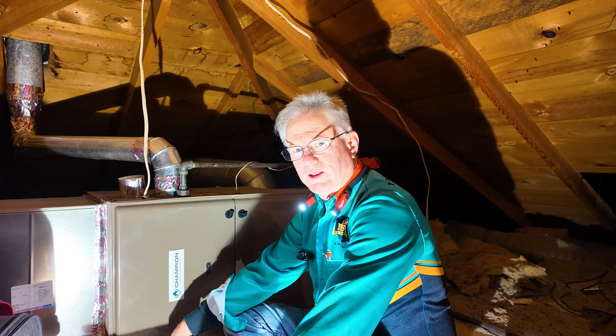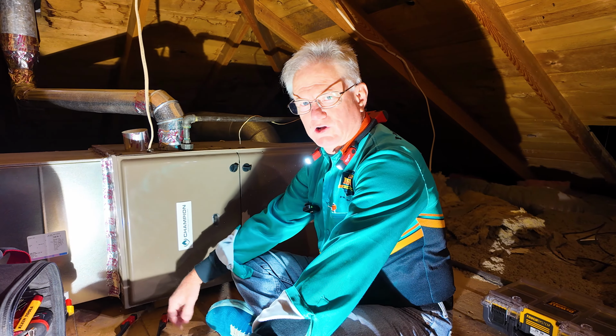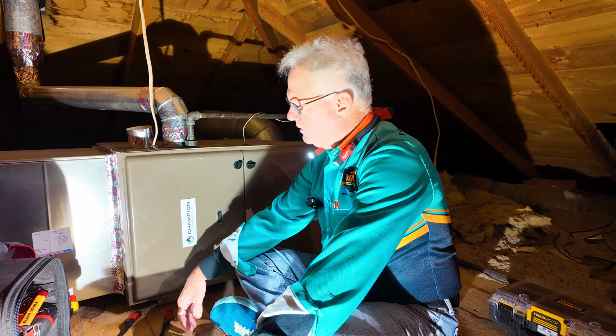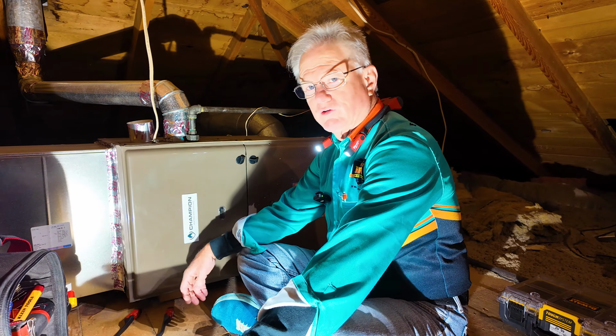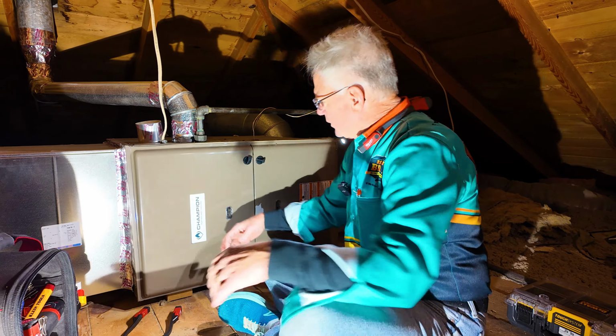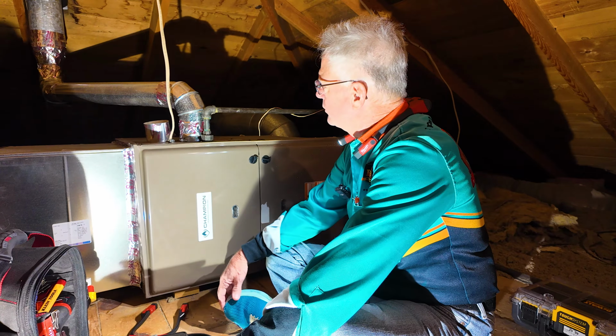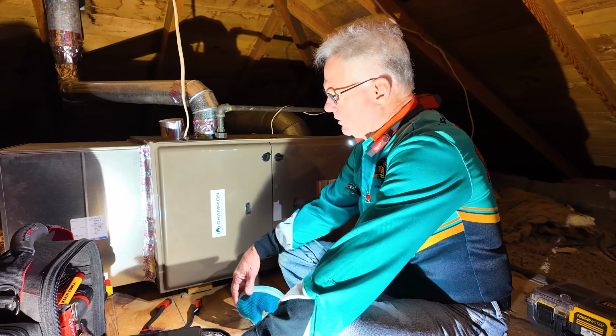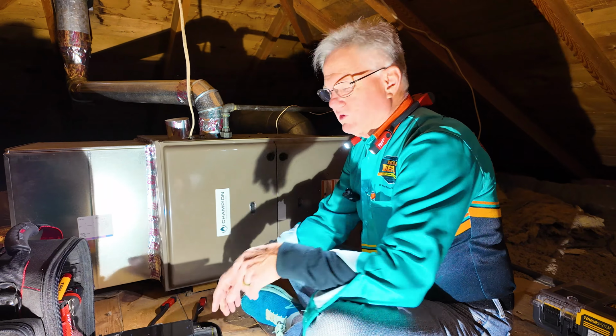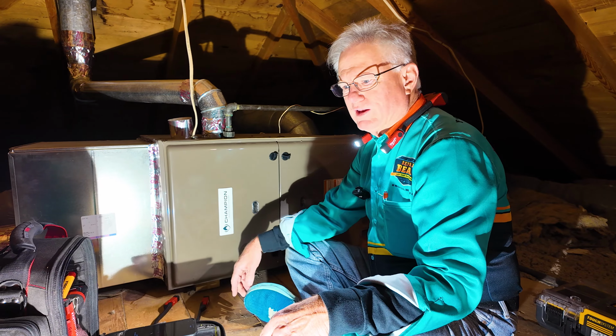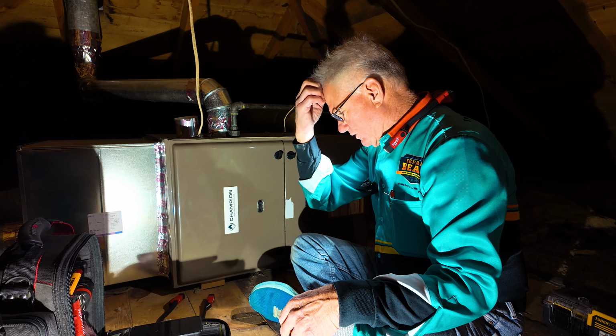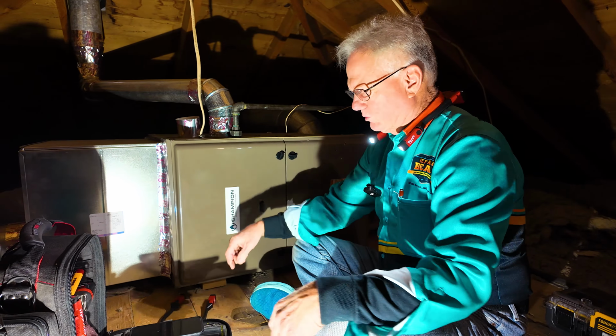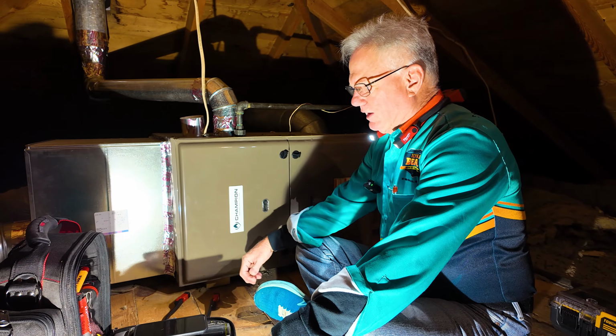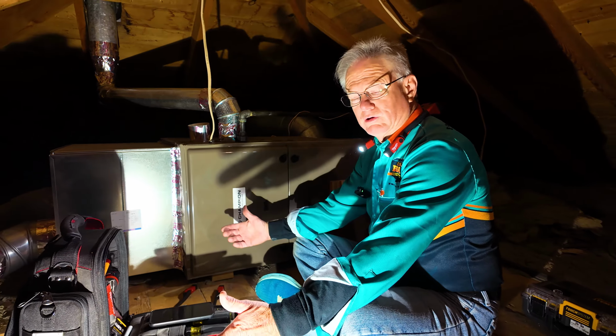Okay, I'm going to do a furnace no heat call that we just got. This is a gas forced air furnace, obviously. It's only a couple years old. The homeowner woke up this morning and said that it was 60 degrees inside and the furnace was not coming on. So I came on the call, they had turned the thermostat off. I turned the thermostat back on and it immediately worked.